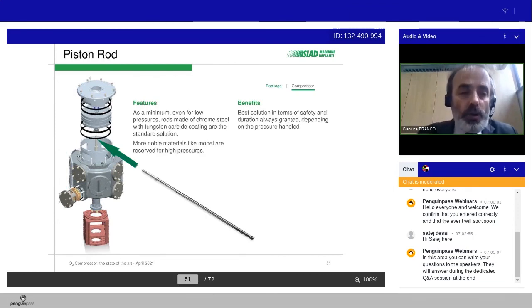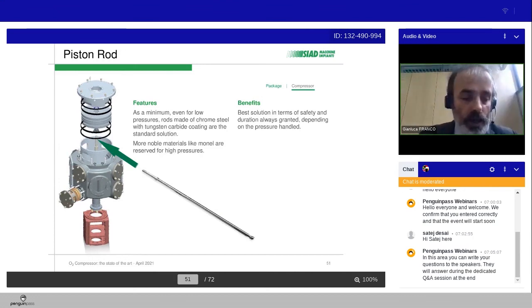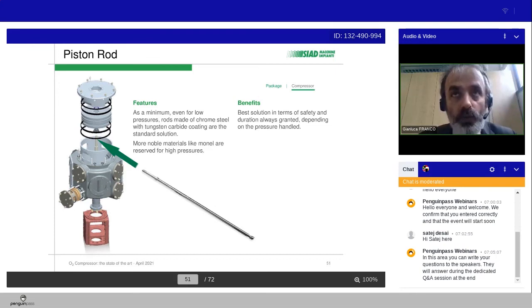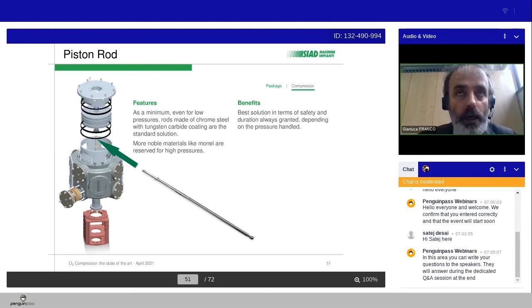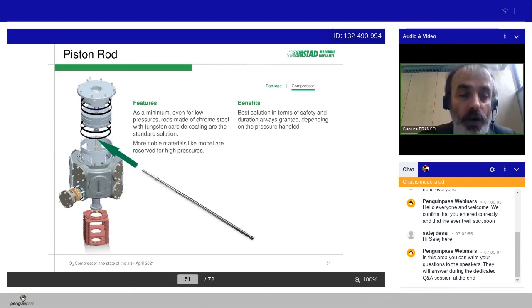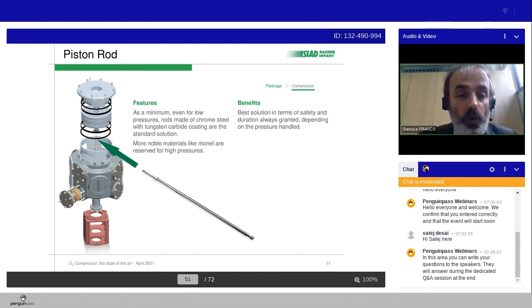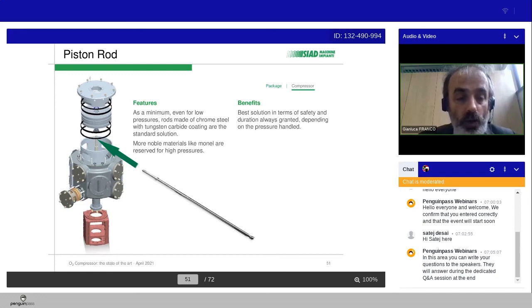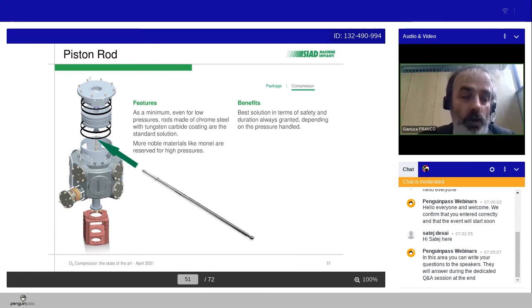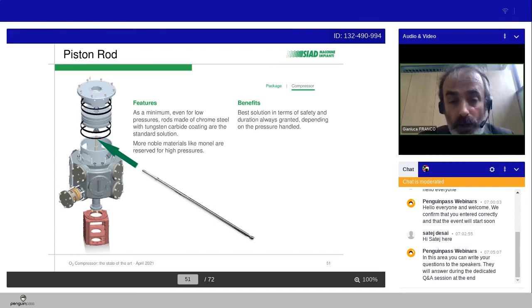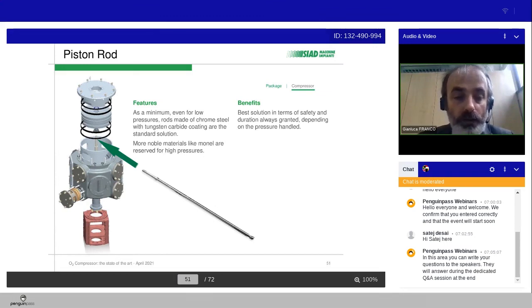About the piston rods, the size of the piston rods change according to the size of the compressor. So we can go from 25 millimeters for the smaller frame, the T-type, 75 kilowatts, up to the 60 millimeters of the P-frame, our big vertical frame. But as a minimum, even for low pressure, rods made of chrome steel with tungsten carbide coating. So this is the standard solution to increase the mechanical properties of the piston rod. More noble materials, like Monel, can be considered for high pressures. In this case, the benefit is the best solution in terms of safety and duration always granted, depending on the pressure handled.